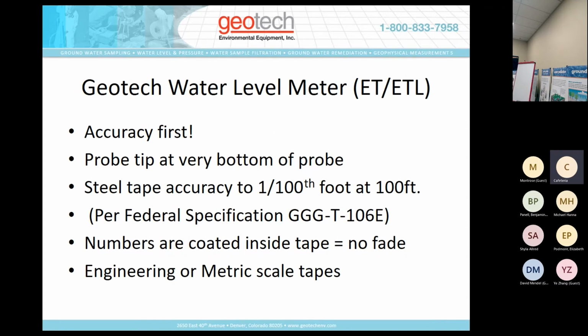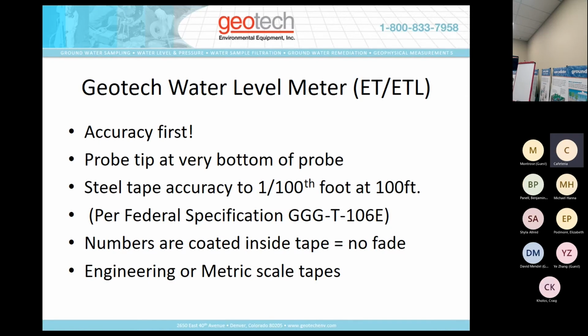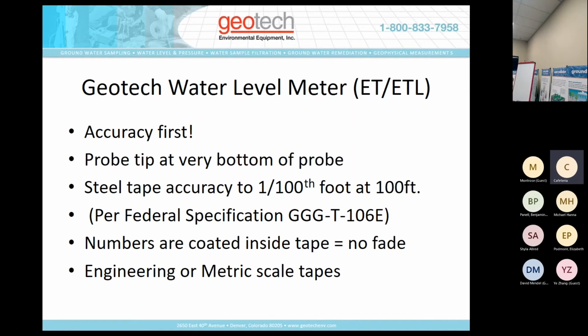The thing that sets apart the Geotech water level meter from a lot of others that may be on the market is the measuring point is at the tip of the probe. When trying to gather good water level measurement data, displacement could be an issue. There's some probes where the conductivity device is in the center of the probe, which doesn't seem like there would be much displacement, but the narrower the well, the greater the displacement potential. So having the measuring point at the tip of the probe is pretty important in terms of accuracy. The tapes, again, metric and engineering scale.